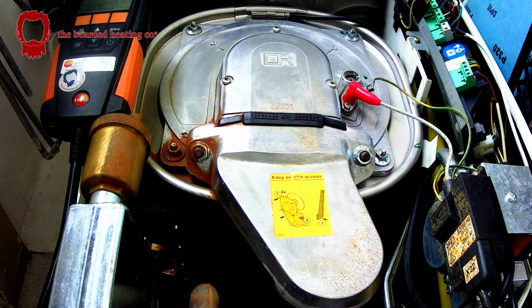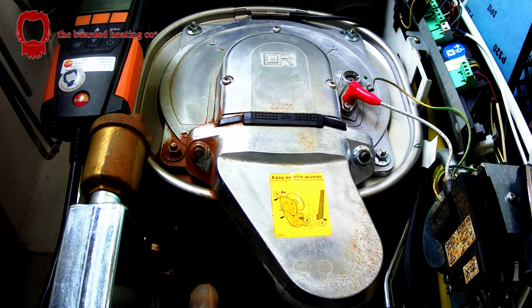Okay, and that's dry. Yep, that's dry. Perfect, that's what I want to see. I carry out a combustion analysis literally on every boiler I touch. Even if I go into a property where I haven't physically worked on the boiler, I will still at least carry out an FGA test just to make sure it's all set up correctly and working well.